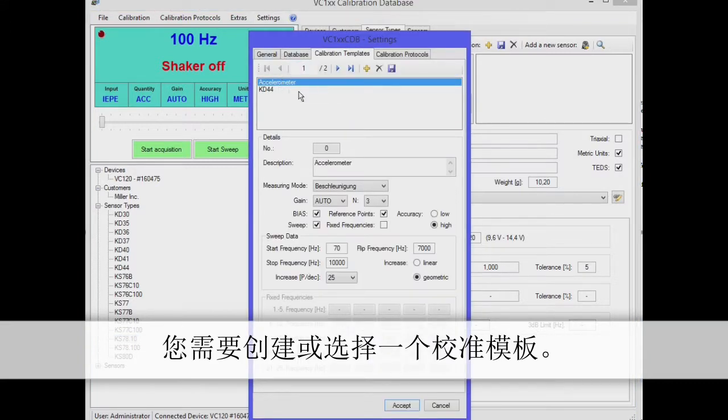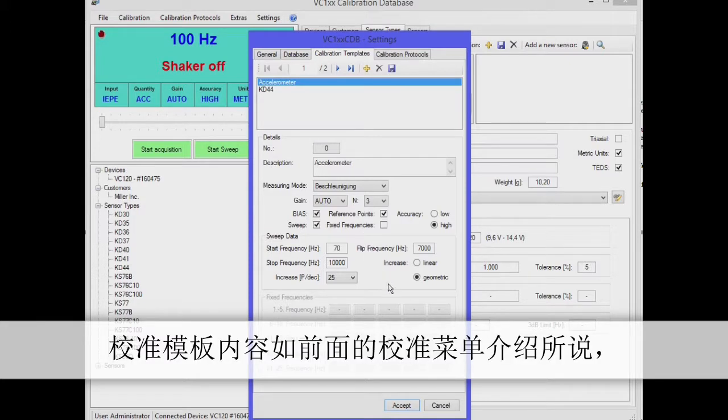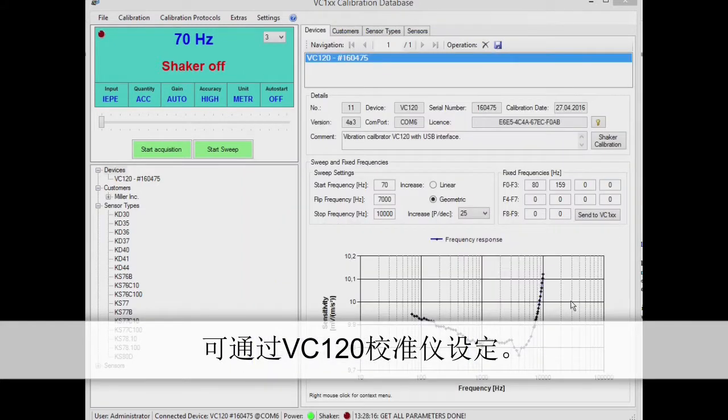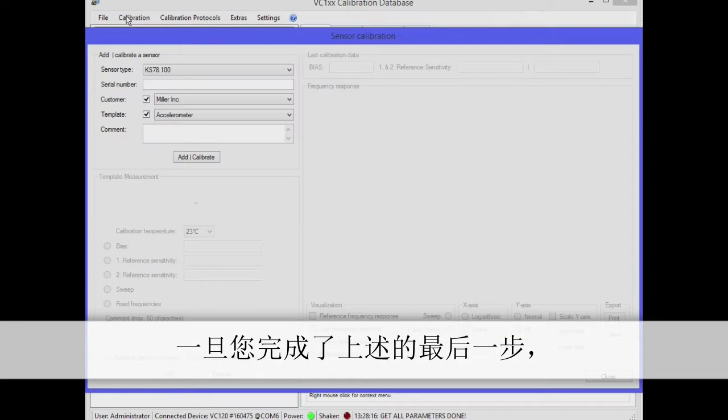Before you start the calibration, you'll need to create or select a calibration template. To do this, click on settings, calibration templates. The calibration template contains the settings to be applied on VC120, as previously introduced with the manual calibration.